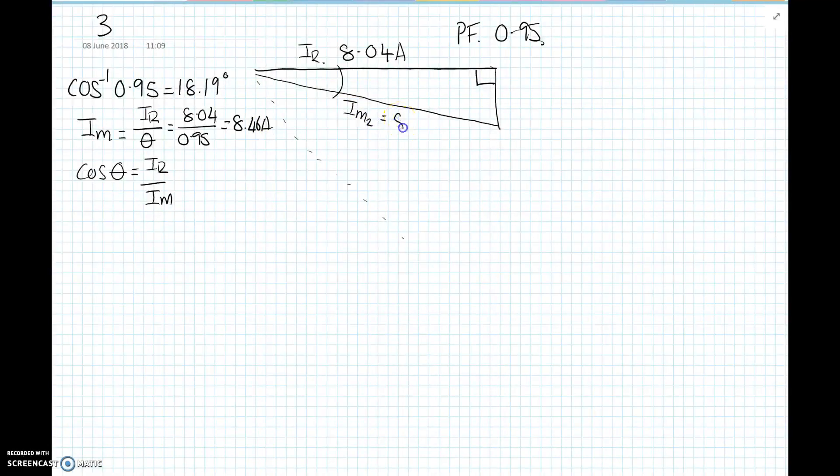So now using our trig functions we can work out the others. The new motor current IM is going to be, the cosine of the angle is the adjacent IM. So IM is going to be IR divided by the cosine factor, which is going to be 8.04 divided by the new power factor 0.95, which gives us now 8.46 amps. So that's much better. So now IM2, because it's been improved, is now 8.46, whereas before it was 12 amps. So we've saved a good three and a half amps there.